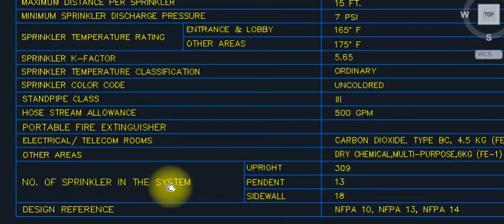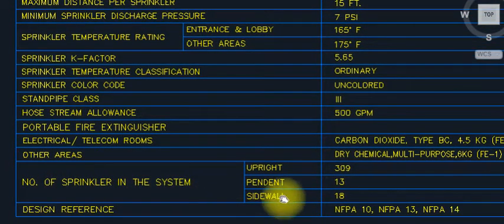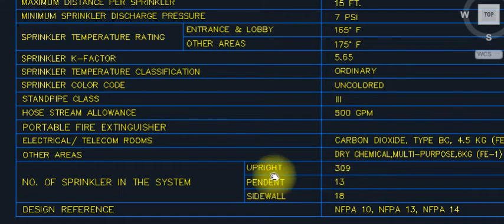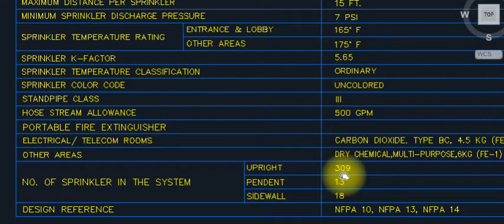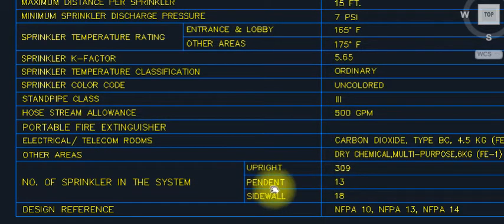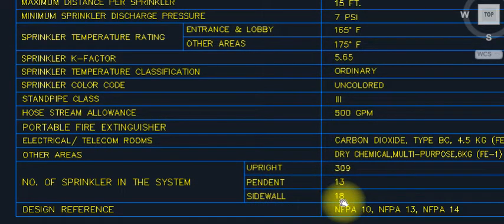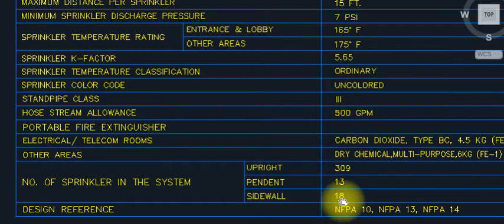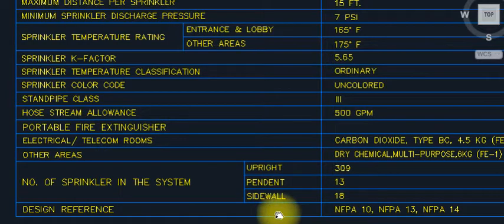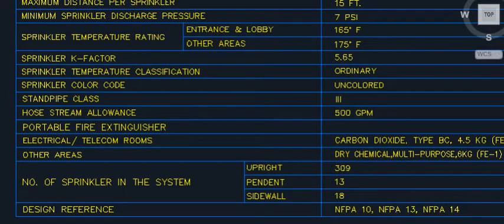Sprinkler quantities in the system — upright, pendant, and sidewall. This is basically a parking area. We are using 309 upright sprinklers, 13 pendant, and sidewall sprinklers in the ramp area. Sidewall is always used in the ramp area — don't forget. Design references: NFPA 13, 10, and NFPA 14.